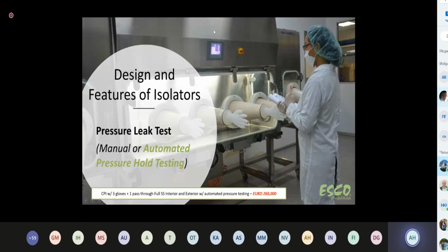You run the isolator as a first step. There will be air that will pressurize the inside. All the gloves will extend outwards like this. And then you wait and see whether the pressure stays positive for a certain period of time. Just a reminder that in a cheap isolator, you have to do this manually. You have to climb up a ladder and close the damper. Or you can have fully automated pressure hold testing via the PLC. We are only offering automated pressure hold testing for convenience. Just a reminder, this would be the cost of a 3+1 glove isolator.